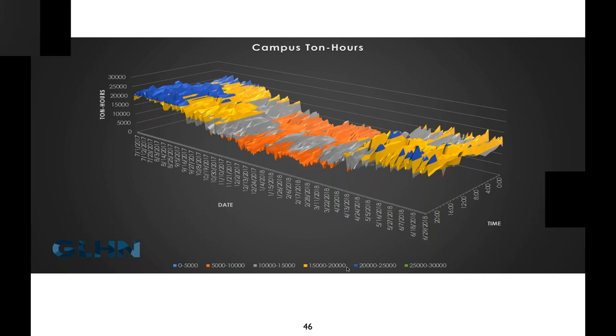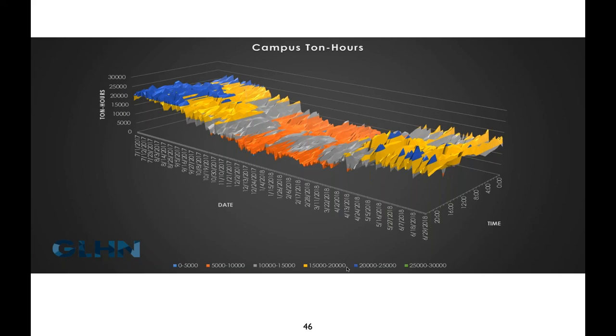That's where we get to see something like 30,000 tons on the hottest day of the year here at the U of A. If you look at the volume under this surface, what's underneath it? Well, that's the total amount of ton hours, the total cooling load we're pulling out of the campus over the course of a year.